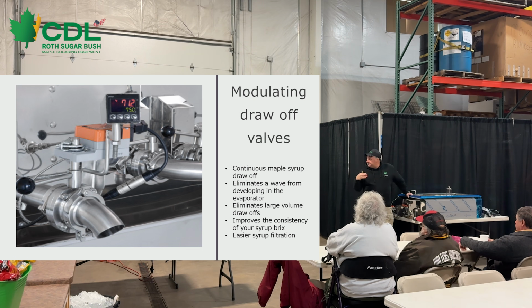So I'll give you an example. I run a 4x14 gas-fired evaporator. Once we get our flow started on our evaporator, say, once we get through the first draw-off, and we have our flow established, our draw-off valve will open up and it may not close for 4 hours. Okay, that's how it should run.